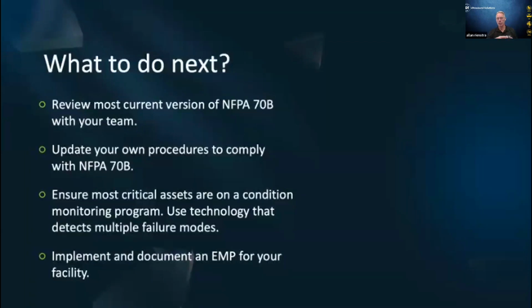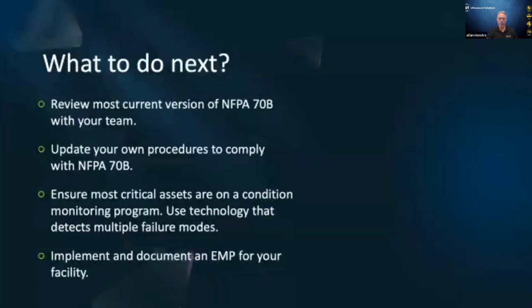And condition monitoring of critical assets will ensure your most critical assets are enrolled in a condition monitoring program. And it's really up to you to define what's critical and what's not critical. But for me, criticality boils down to: if I lose an asset, what's the impact? Again, going back to the hospital example, if I lose a transformer, I might lose lives. In manufacturing, if I lose a transformer, well, I know that for some transformers the delivery time is anywhere between 12 and 18 months. So imagine yourself not being able to manufacture your product for 18 months while you're waiting for your OEM to supply you with a replacement transformer. So define criticality however you want to. I don't define criticality by the cost of the asset. I define criticality by the impact of not having that asset available, not having that asset reliable. What's that impact going to be on me and my organization?